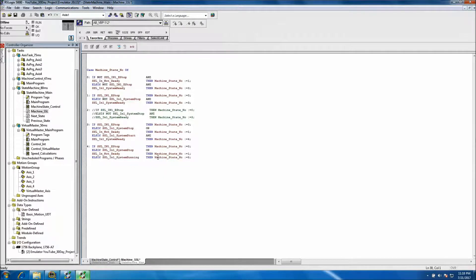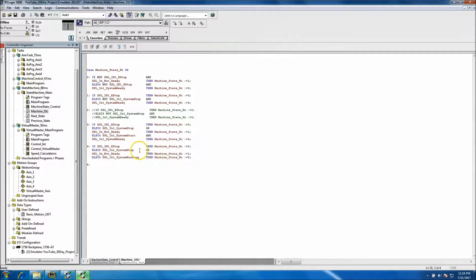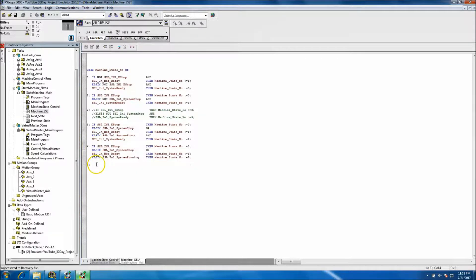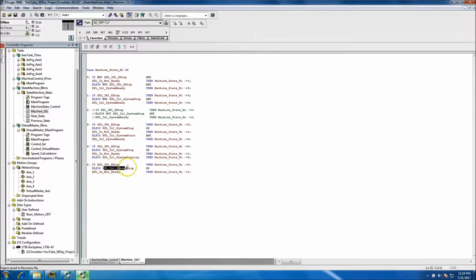Now we have State 5. State 5 is basically just going to have e-stop, stop button, or not-ready conditions. In the instance that it's running in State 5, the only things that can stop it are the e-stop, the stop button, or the system not ready. We can grab that logic and paste it right there.